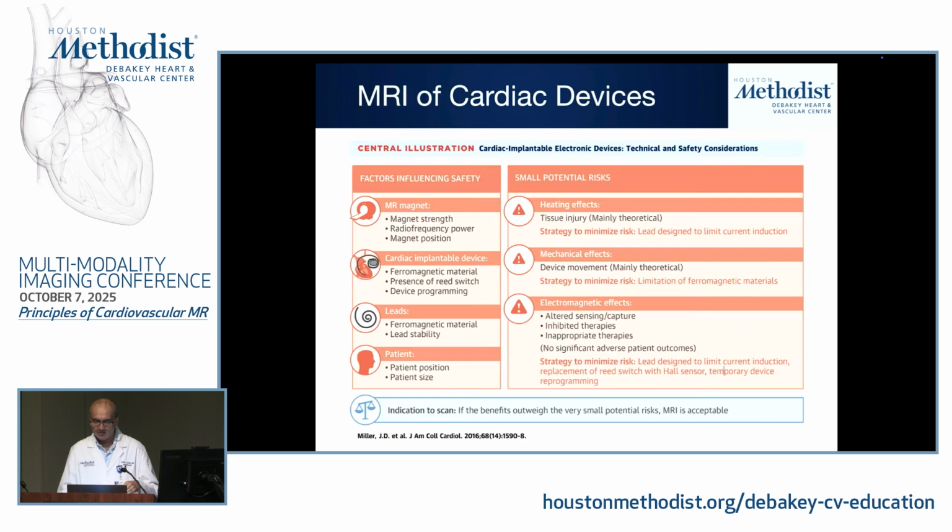Now, what are the concerns with MRI devices? Obviously, there are several things you worry about. One is heating. If you have metal, when you apply these radio frequency waves, could that metal absorb those waves, and could that cause heating? If the device heats, you may say, well, what's the big deal? Is it going to malfunction? It's not so much about that. It's could it then cause heating of the tissue in the human body around the device?